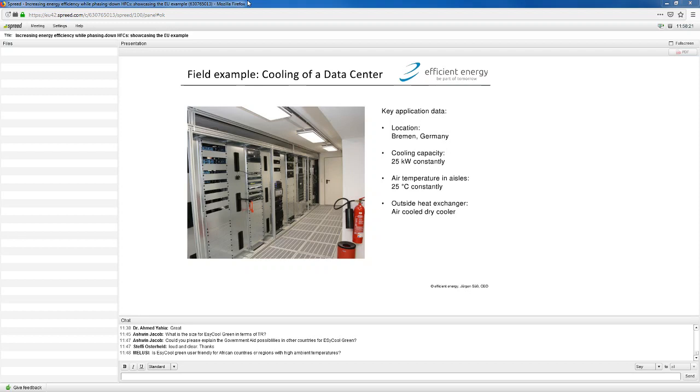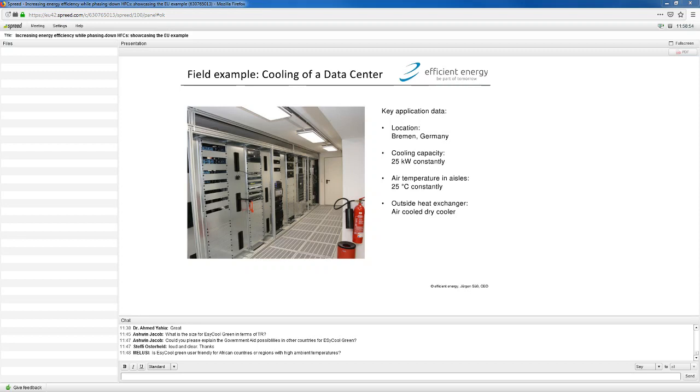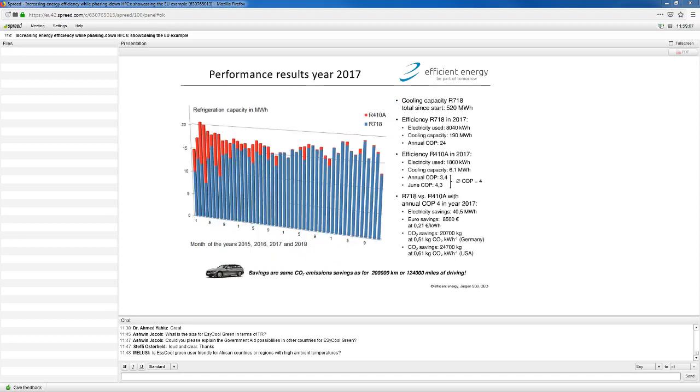In a server room in Bremen, which is in the north of Germany, they had a cooling capacity with the servers you can see here of about 25 kilowatts. They had a double floor indicated by the grid in the bottom, and this is the cold aisle. They wanted to maintain 25 degrees C, and the outside temperature in Bremen varies, maximum up to 30, so you have a lot of free cooling time. The servers just took the air and blew it on the other side, which is the warm aisle, and there was about 35 degrees.